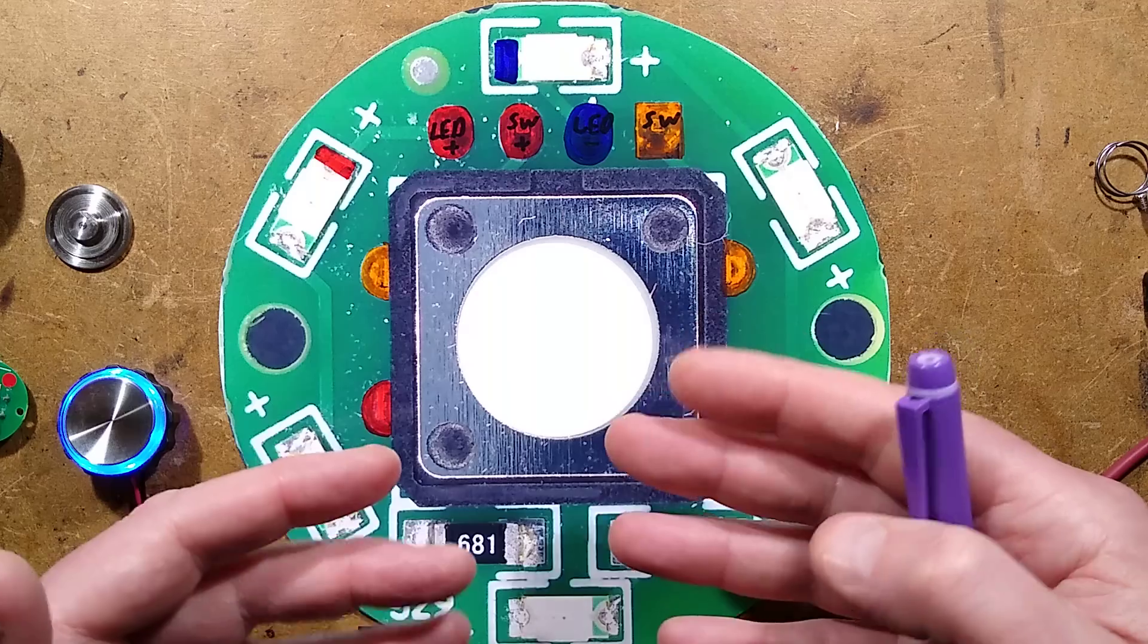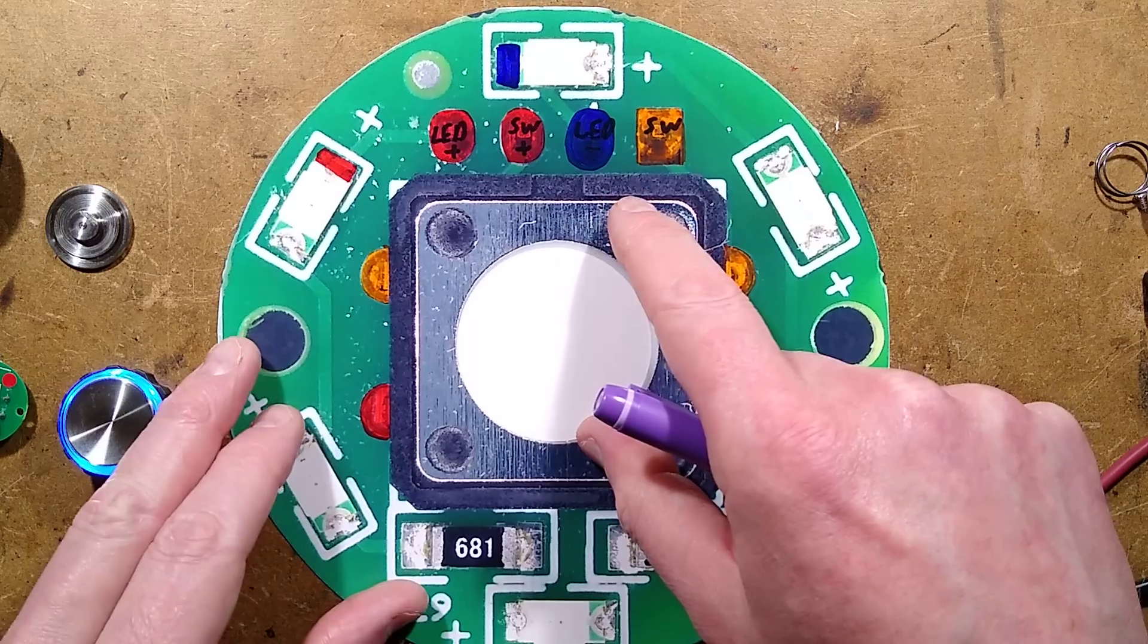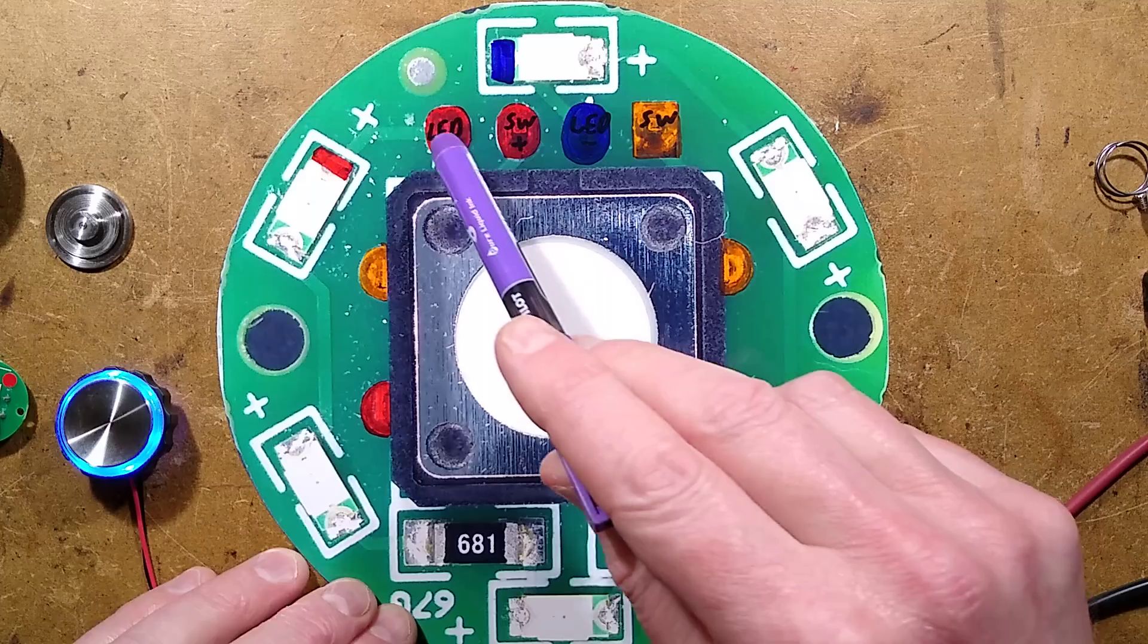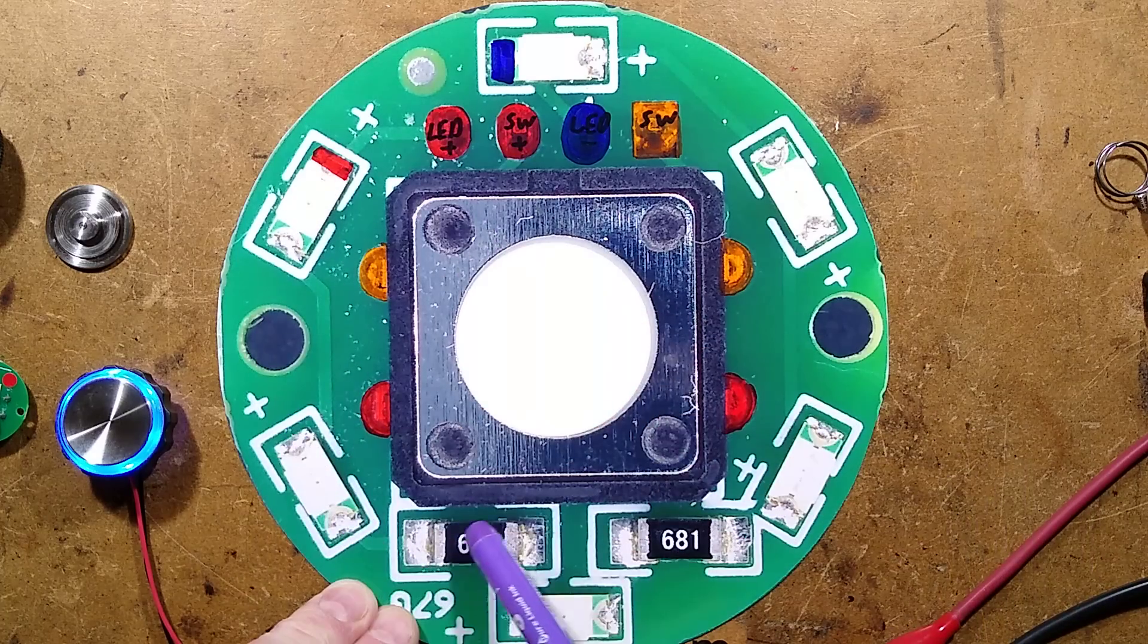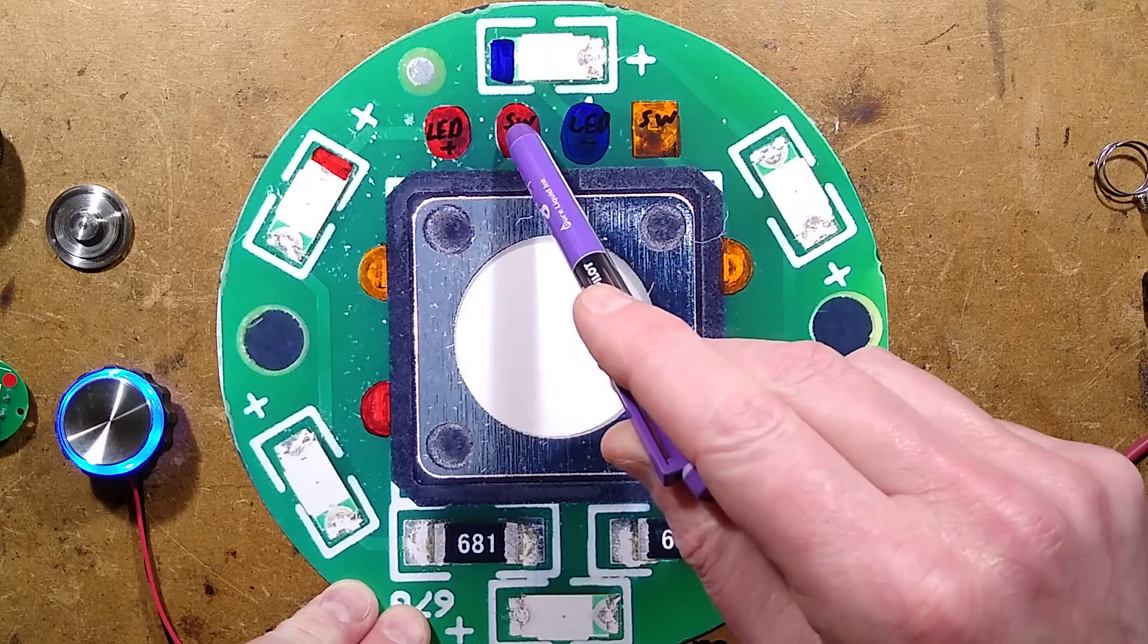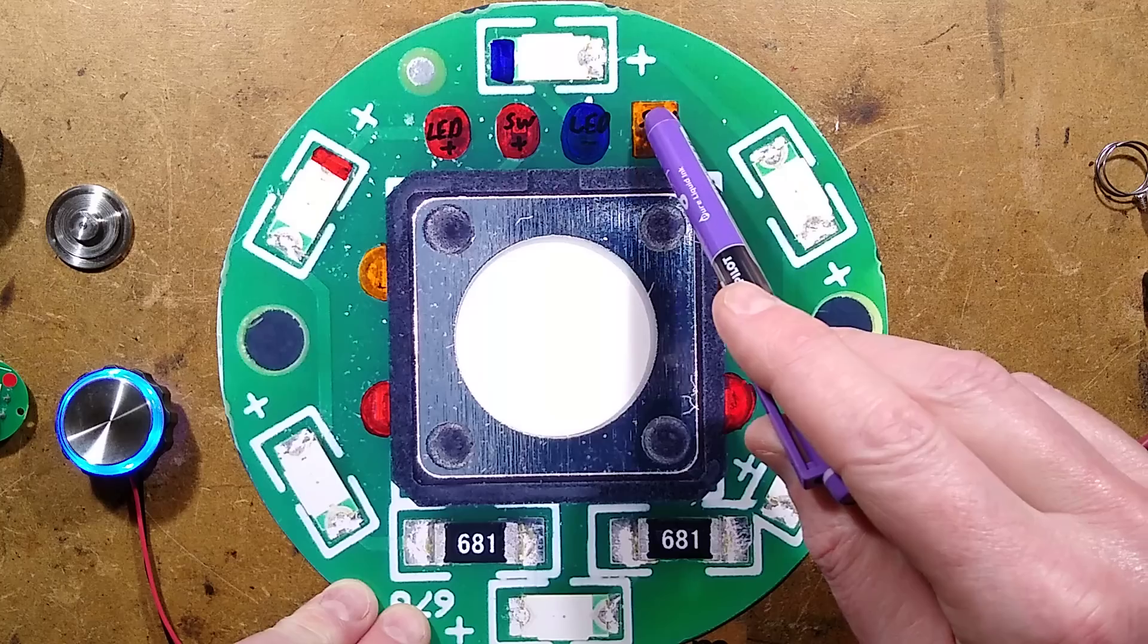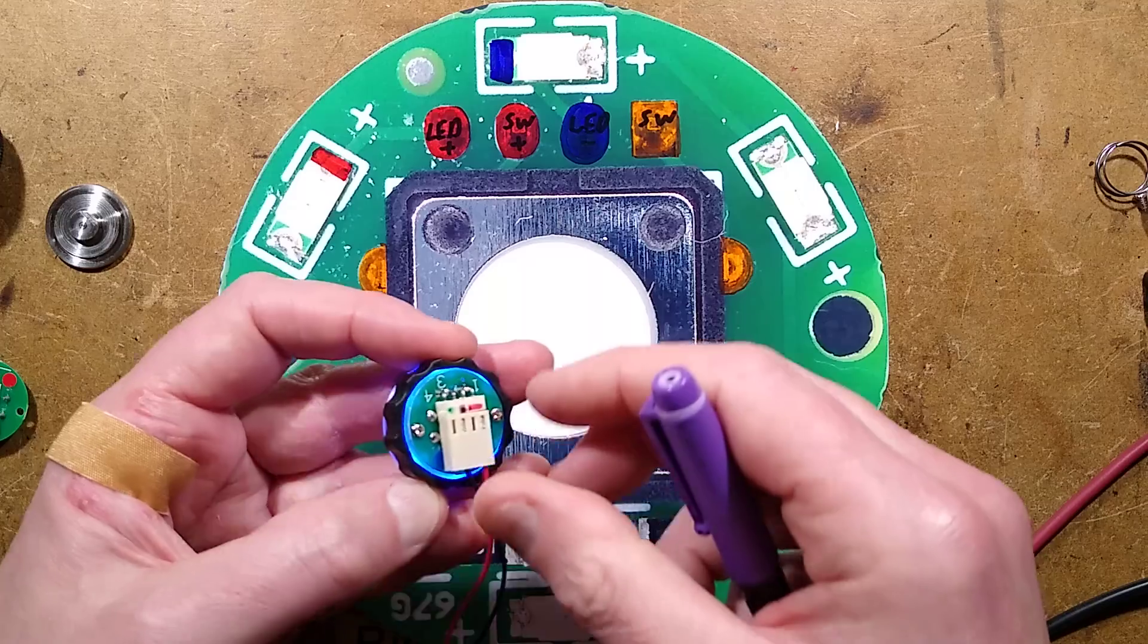I guess that some just use a common positive and then sink the LED to the zero volt rail to illuminate the LEDs and just have the switch input from that same 24 volts. But here's the configuration. We've got the LED contact on the outside here which then goes through the LEDs, through resistors, through the other LEDs and then back to this pin, and we get the switch contact which goes to the bottom two contacts here and the return - that's the switch positive and the switch return which goes to that contact. This is useful if you want to use these buttons, just you know what goes where.